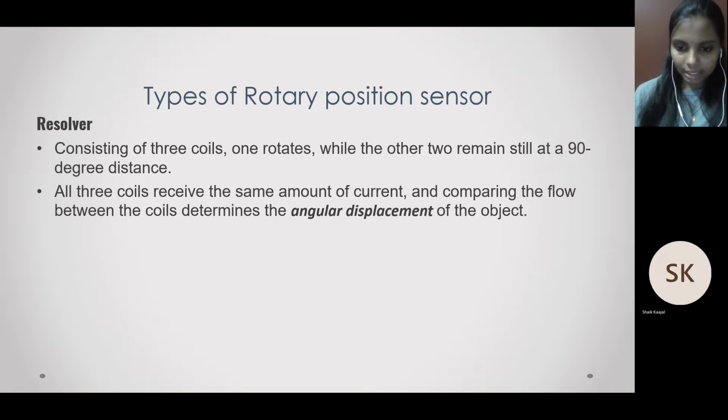The primary winding is linked to the rotor, while the secondary windings are oriented at 90 degrees and linked to the stator. An AC voltage is induced in the primary winding to excite the coils. Back EMF generated from the primary winding is further induced in the secondary windings with sine and cosine outputs respectively. Such outputs are further processed in an ADC converter for general digital signals. Resolvers are commonly interfaced with motors.